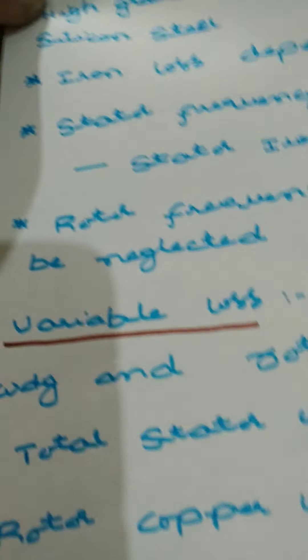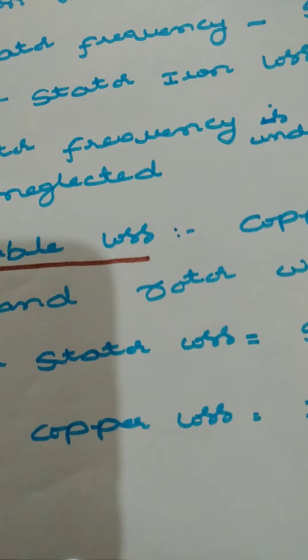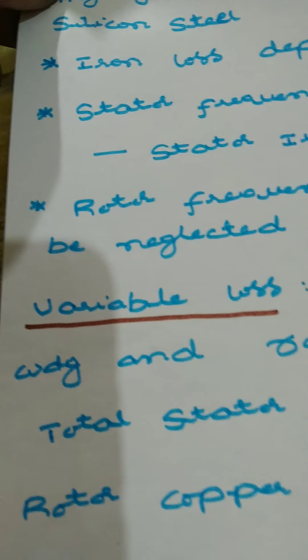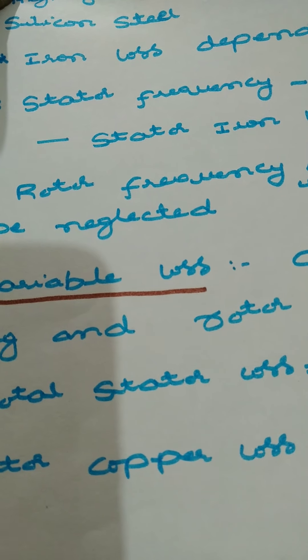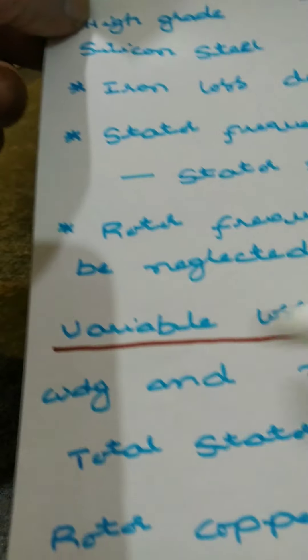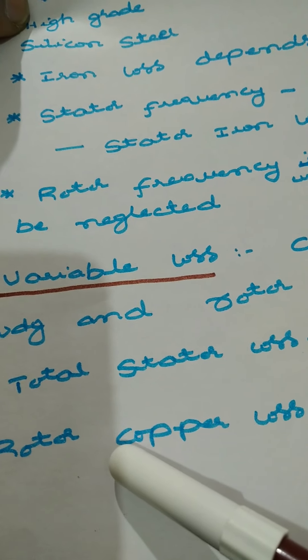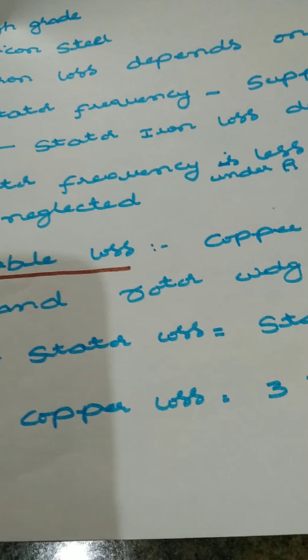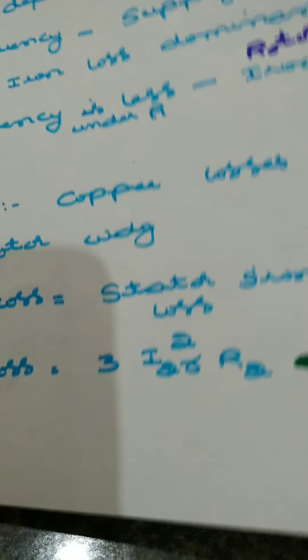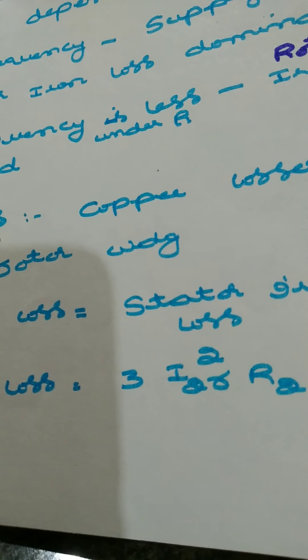Copper loss changes depending upon the load condition. As you put the load, the current drawn from the supply changes, stator current changes, and rotor current is also changing. Due to that, losses take place in the stator winding and rotor winding. Total stator loss is nothing but stator core loss plus stator copper loss. On the rotor side: rotor copper loss plus rotor core loss — but rotor core loss is neglected because under running condition the frequency is less.